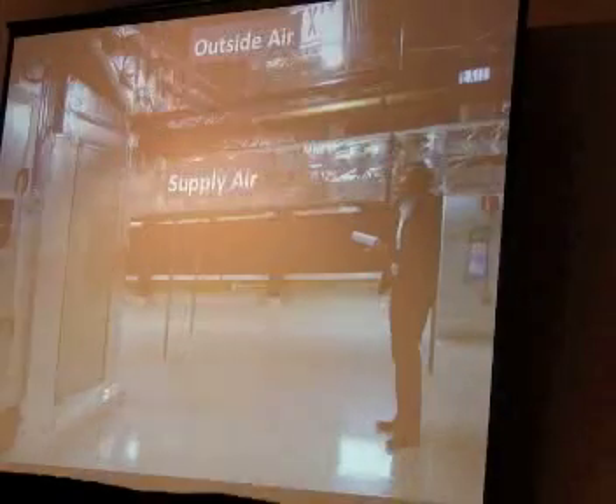So the first thing we're looking at is CO2. These CO2 sensors are about $1,500 apiece, all throughout the building. The easiest thing we're doing conceptually is measuring the fraction of outdoor air supplied in the mechanical systems for each floor, at 5-minute intervals. For each data point we're collecting, we'll have about 100,000 time series data points after the year of sampling, for each type of measurement. So it's a lot of data.